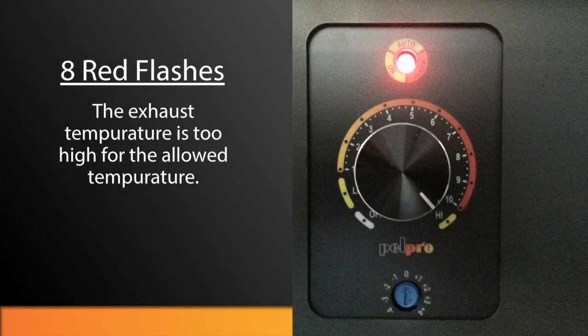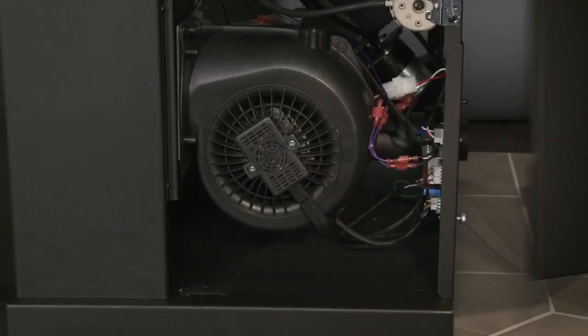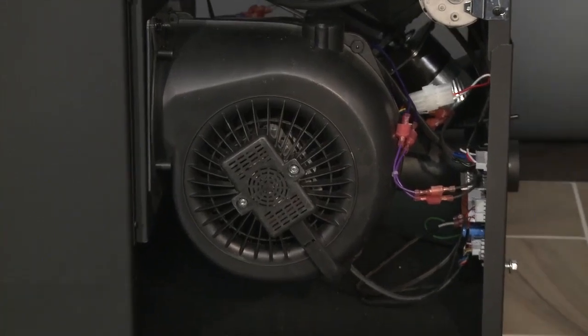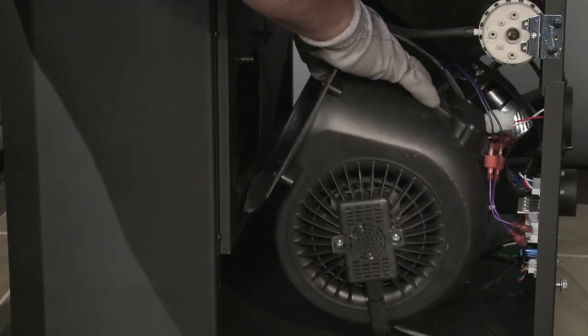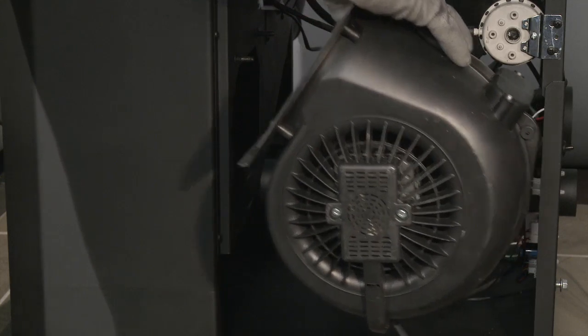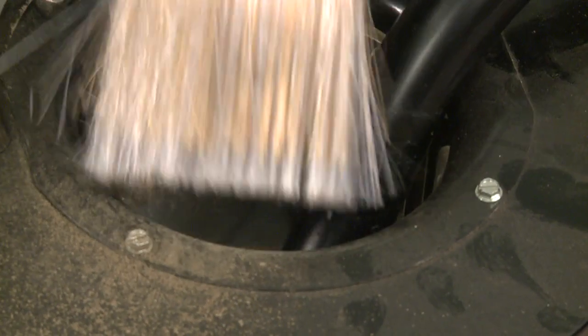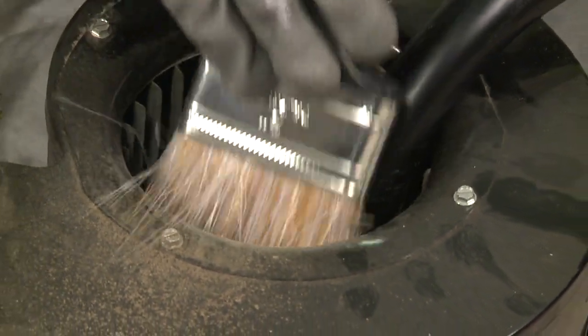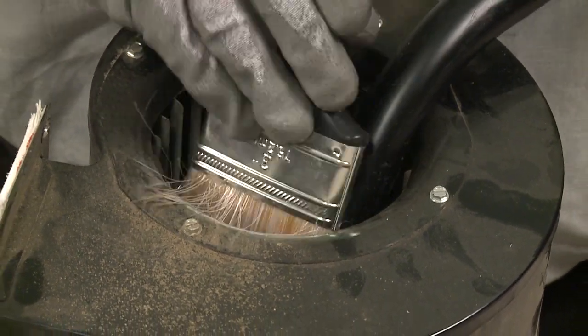8 red flashes means the exhaust temperature is too high for the allowed temperature. This may mean that the convection blower is dirty. Clean the convection blower and return it to the unit. If this does not solve the issue, the convection blower may need to be replaced. Watch the convection blower cleaning video to see how to properly clean the blower.